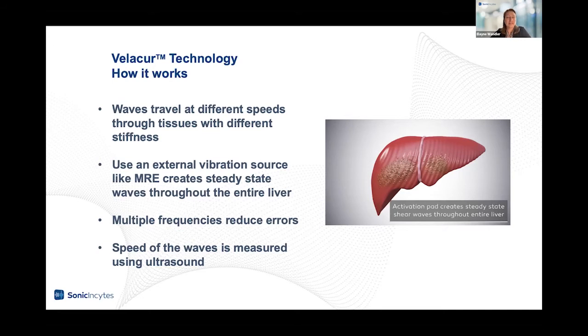So what are the features that make Velacur work so well? Like MRE, the waves are created using an external excitation unit, which allows for the creation of steady state waves, meaning they're constant throughout the entire liver. This is in contrast to other systems that generate the wave from the probe through a pulse, where the wave only goes through a section of the liver. We also activate the waves using four different frequencies, which helps eliminate potential errors caused by artifacts that might interfere with an accurate wave measurement if only a single frequency was used. Further, the steady state shear waves traveling throughout the entire organ allow for a much deeper measurement, meaning greater accuracy on patients that may have a high body mass index.